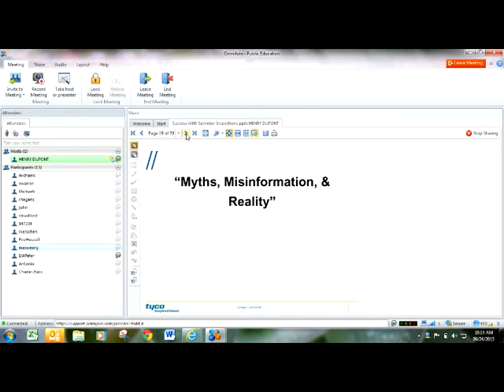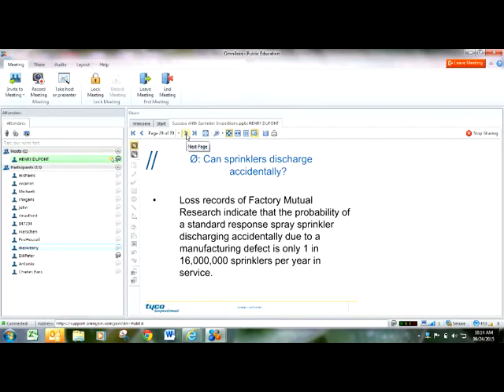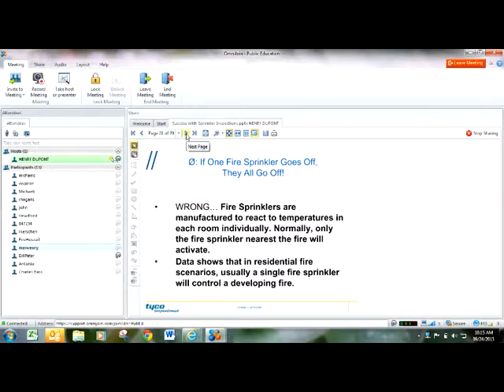Misinformation about sprinkler systems. According to Factory Mutual, only 1 out of 16 million sprinkler heads per year in service go off for no reason whatsoever. Sprinkler heads do go off due to being struck, uninstalled, and then reinstalled. It's easy to damage a sprinkler head, and then it can seemingly go off because of a defect at a later date. Well, it's seldom ever a defect. It's damage. If one sprinkler head goes off, they all go off. That's not correct either. That only happens on TV. And clean water rarely ever comes out of a sprinkler head. If you watch TV, you see them all go off at the same time and clean water comes out. That's a myth.